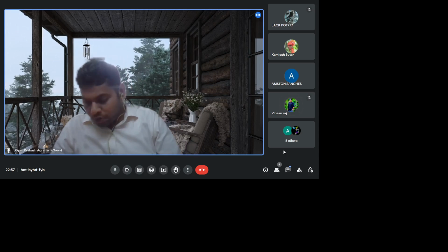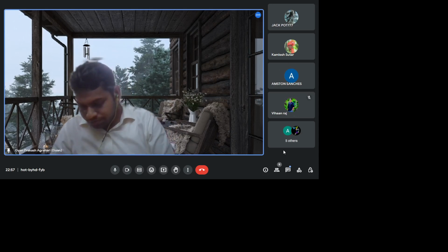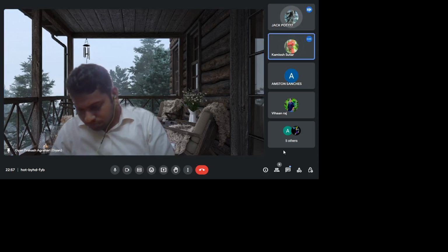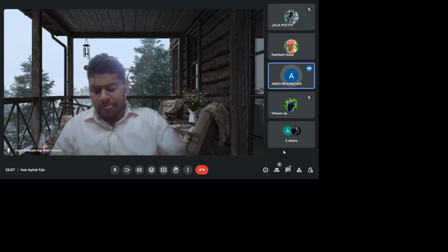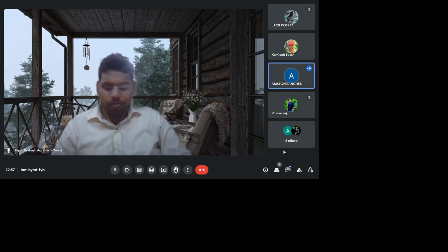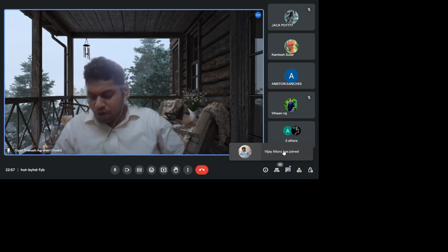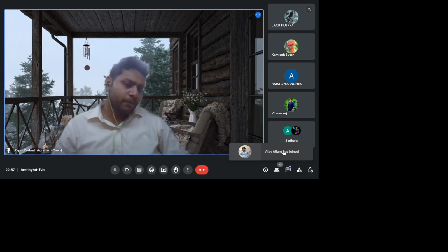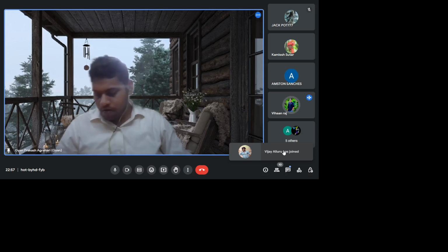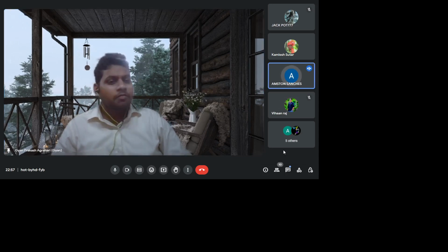Okay, now we have the boiler blow down valve. Can anyone guess the location of the boiler blow down valve? Bottom. It's at the bottom, connected to the water drum, and it is used to discharge the boiler water and sludges. Also, in the case of inspection, you have to use it.